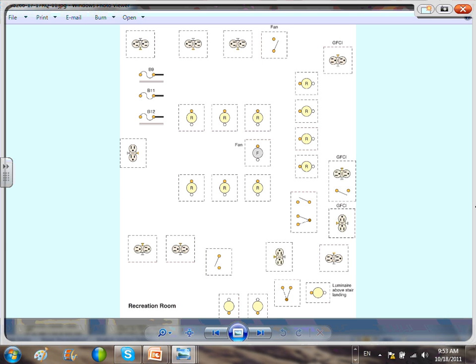How many circuits? We can get away with 1 circuit if we decided to put just 1 light in the middle of that room and call it a day. 1 circuit with all the receptacles. They have a sink, a bar sink. Bar sink, guys, the code says if you're within 6 feet of any sink, you have to have a GFCI receptacle. How many circuits do you need for the bar sink? The code doesn't say anything about it. The rule that I told you guys, no more than 10 receptacles or lights in 1 circuit, if you apply that, you probably end up with 3 circuits. Is it overkill? Yeah, they're making it an entertainment room. They're not making it just any recreation room for kids or whatever. You know, there's a bar there, there's entertainment.